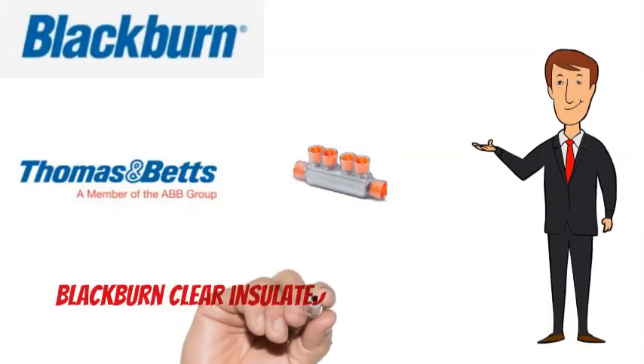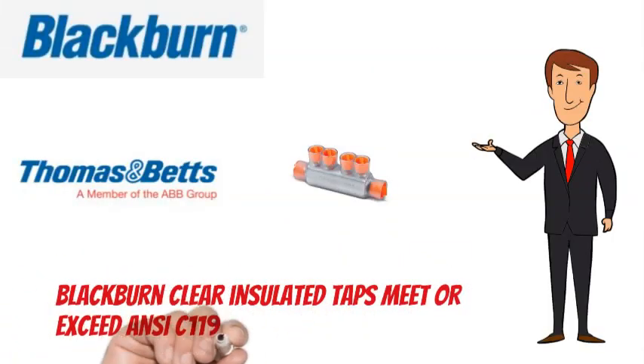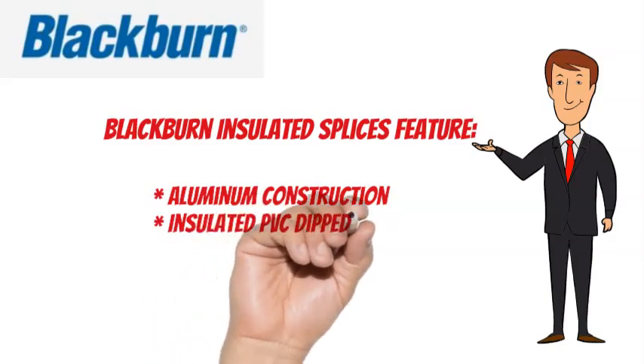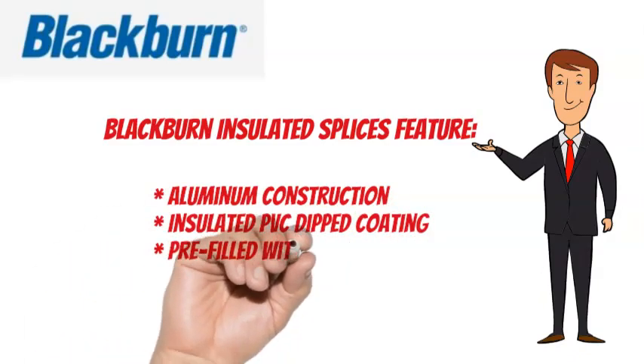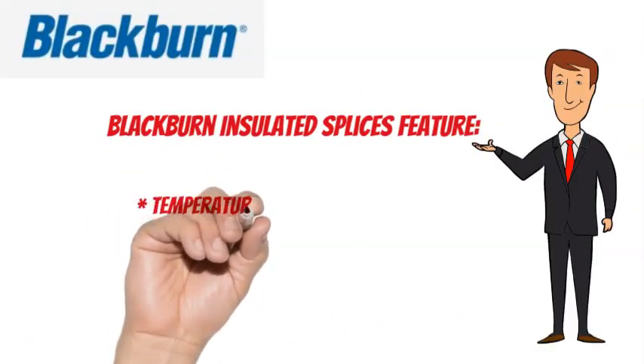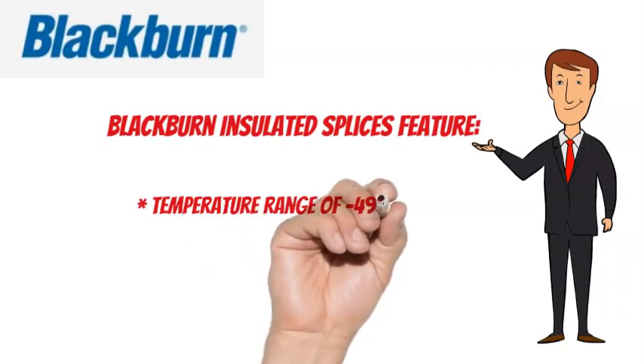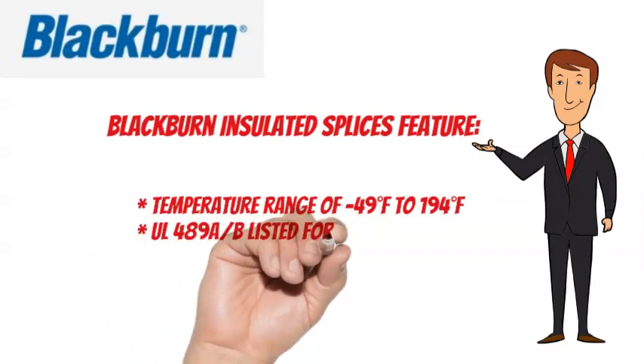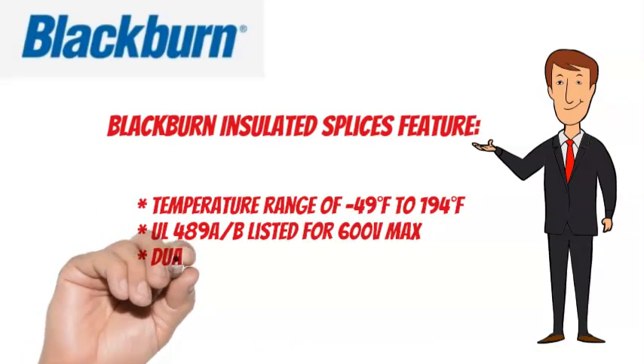Blackburn Clear Insulated Taps meet or exceed ANSI C119.4 specifications. Blackburn Insulated Taps feature aluminum construction, insulated PVC dipped coating, pre-filled with oxide inhibitor, and meet or exceed ANSI C119.4. They have a temperature range of minus 49 degrees Fahrenheit to 194 degrees Fahrenheit, are UL 489A/B listed for 600 volts max, and are dual rated.